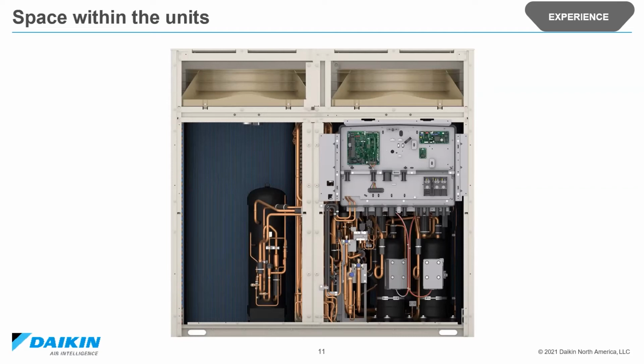The control system now has a built-in data recorder, and this is a really big advantage. It can store up to 45 minutes of operational data, and that data can be used to diagnose any problems that were to arise in the case of an error code. And it'll give you basically the 45 minutes prior to that error code occurring. In addition, the new control system has the ability to detect cross-piping and cross-wiring if it were to occur during installation.